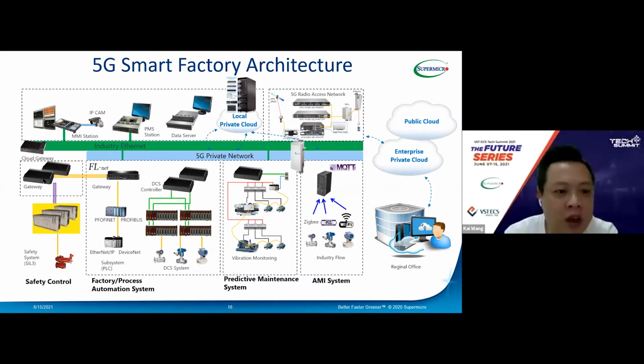Here we have the fieldbus gateways that can connect with those safety systems and bridge that data to the cloud. The factory automation or process automation system can utilize the fieldbus gateway as the IoT gateway to collect data from those sensors. This is predictive maintenance using the fieldbus PC to collect vibration data generated from diesel engines, collected from the PLC I/O, all the way through the Ethernet switch and connected to the IoT gateway.